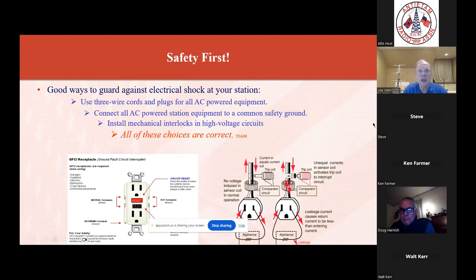On the hot lead of your circuit, what it does is measure the difference between the power that comes out to, say, an appliance compared to what goes in. Now, we talked about before with basic circuits, what goes in must come back out, and that's true, but there's a caveat: if you have a faulty ground, or if something becomes exposed to water and finds another conductive path, you can have what is referred to as a leakage.